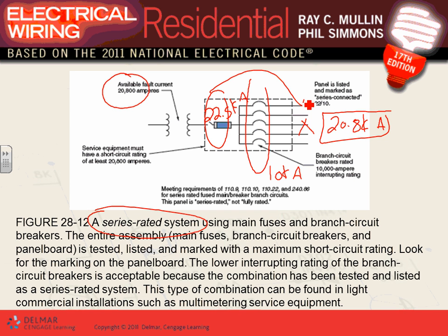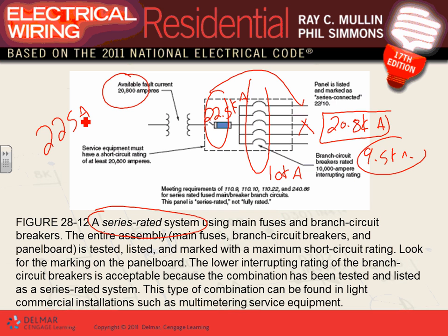If the short circuit on a branch is within range — say 9,500 amps — those little guys can handle it on their own. Series rated systems are typically used for up to 225-amp lighting and receptacle panels. The difference in price between a fully rated and series rated panel could be significant — maybe $1,000 versus $700–800.